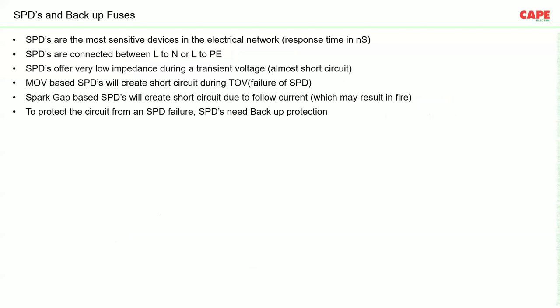Now, SPDs and backup fuse — many people have questions about backup protection. SPDs are the most sensitive devices in the electrical circuit with a response time in nanoseconds. They are connected between line to neutral or line to PE and offer very low impedance during transient voltage — almost creating a short circuit — which is how they create equipotential.